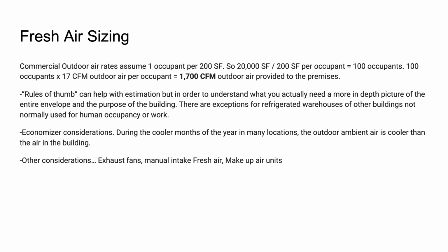What's cycling it? Is there something to just open that when it gets cool for free cooling? All of that, economizer, yep. There's stuff to look at to make sure that you're replacing with what was there. And then, like we mentioned before, making sure, particularly if it's not going back at the exact same height, exact same side of the unit, that you aren't now introducing something that wasn't there before. It happens a lot when you go from an old Lennox to Carrier, it almost completely reverses where the fresh air is. And so now you're next to a vent stack or something, and you get a lot of that stink coming back up inside.